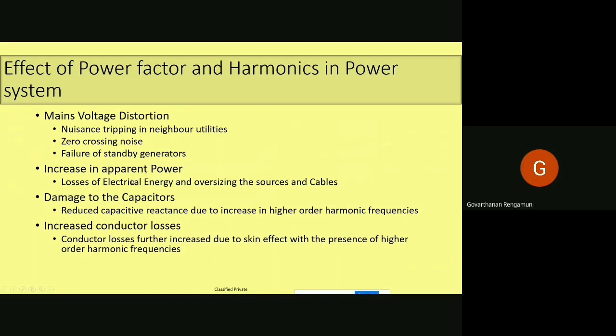Increase in apparent power, because as I already said, if you are injecting more harmonics, your power factor will become very poor. If the power factor is poor, your apparent power increases for the given power. So the apparent power increases means your equipment will be drawing more current than required. Because of that, you have to size the cables and all upstream devices for that increased current rating. So the losses will also be increasing.